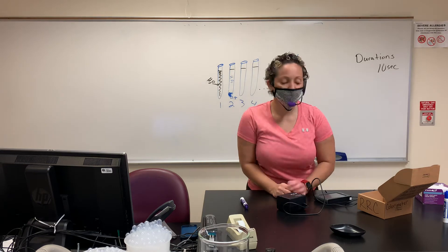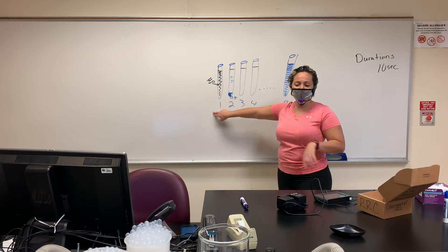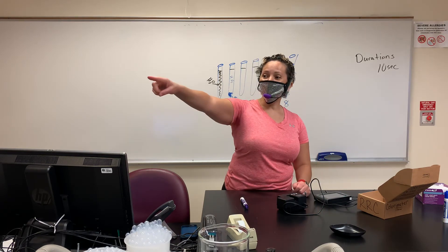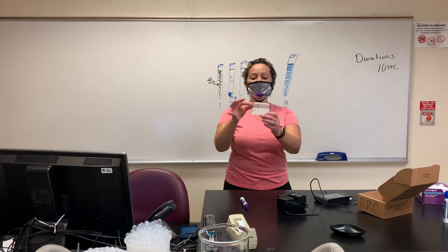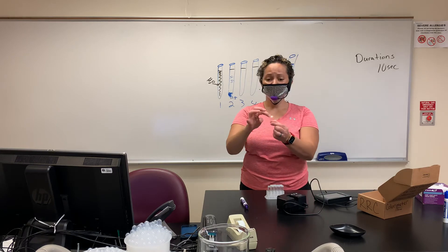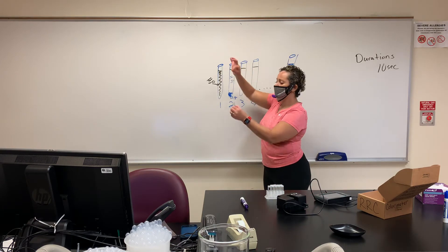The most important thing — we have to calibrate it, and you're going to calibrate it using your water. You're not going to get that test tube in there. What you're going to do is take your little cuvettes. When you number them, number them on the lid — do not number them on the sides. You're going to transfer liquid from your test tube into the cuvette.